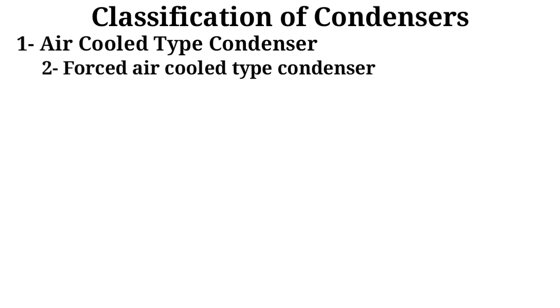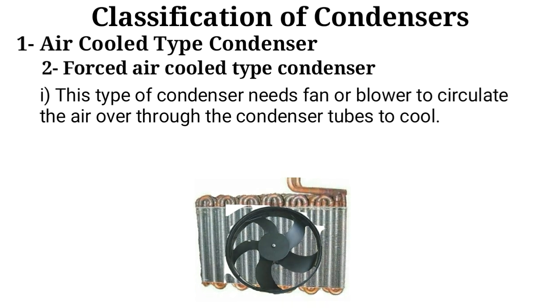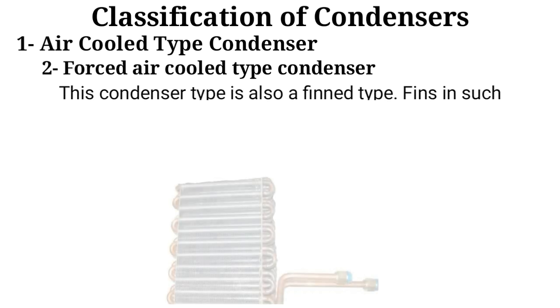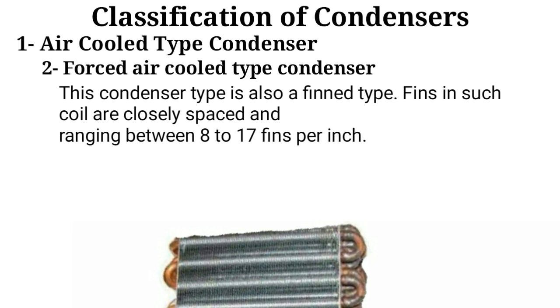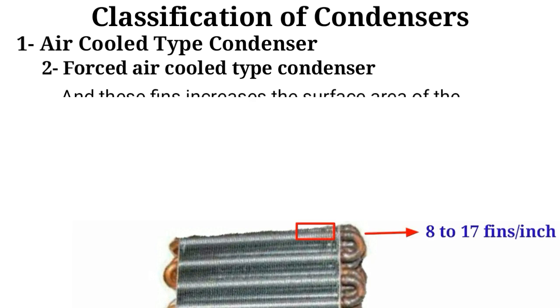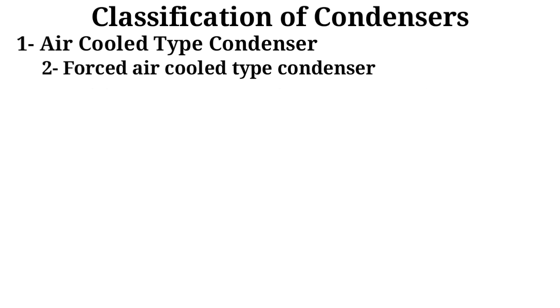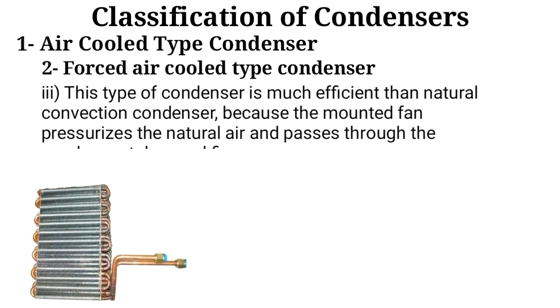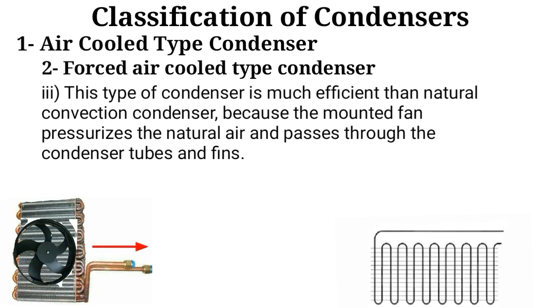Number two: the forced air-cooled condenser. This type of condenser uses a fan or blower to circulate air over and through the condenser tubes to cool. This condenser type is also a fin type, where fins in such coils are closely spaced, ranging between 8 to 17 fins per inch, increasing the surface area. This type is much more efficient than the natural convection condenser, because the mounted fan pressurizes the air which then passes through the condenser tubes and fins.